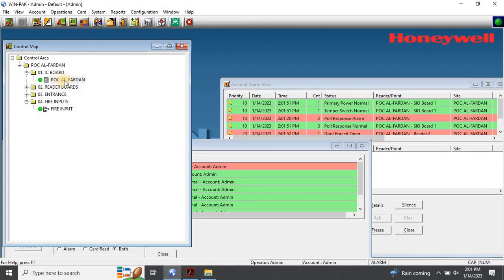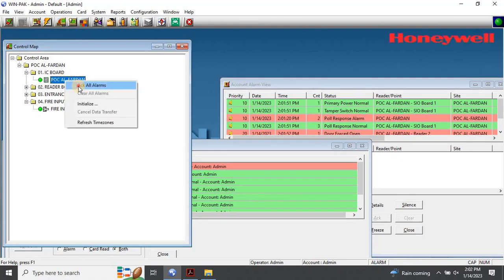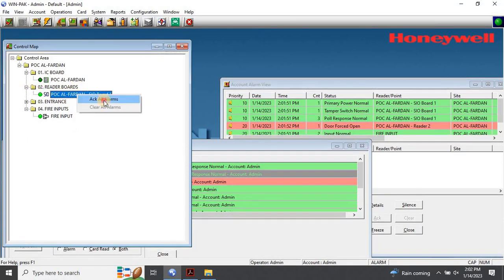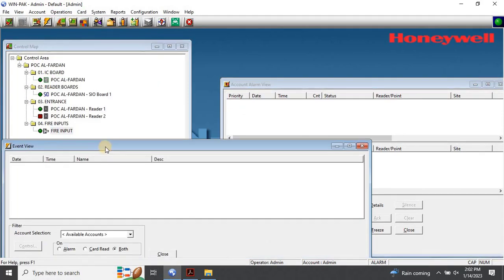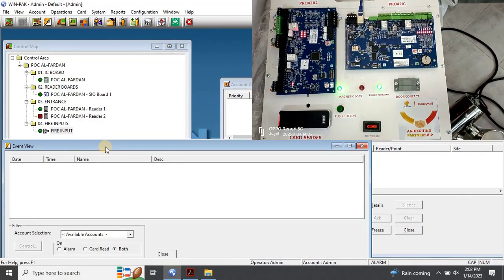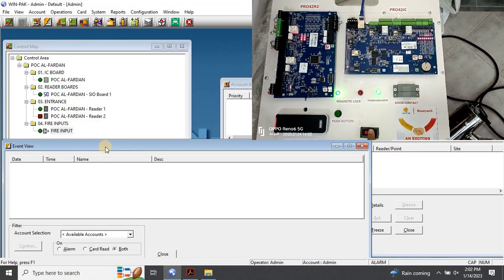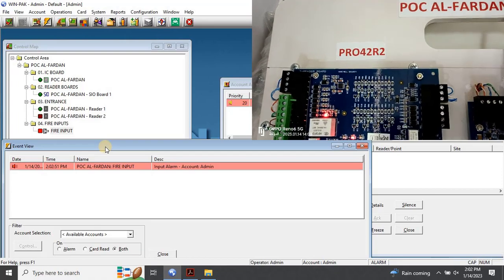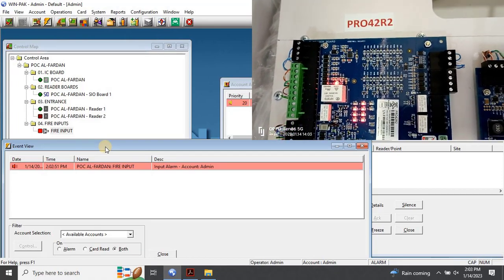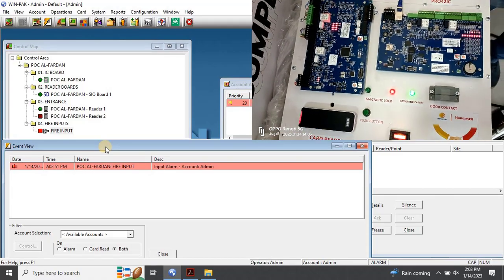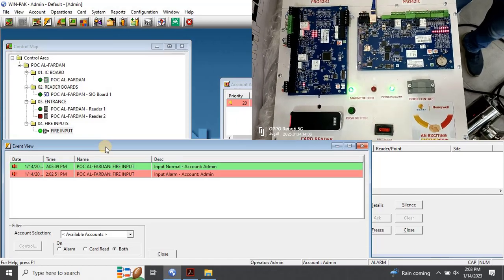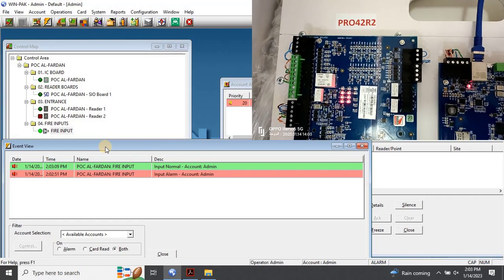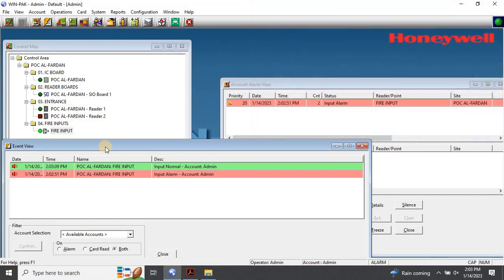Once the initialization is completed, it's time to test the fire alarm interface with the access control system. Before we begin, let's clear all the events for a fresh start. As you can see on the board, once I turn on the fire alarm input switch, the relay is activated and the automatic alarm is generated. The fire input is activated and the fire input indicator changes from green to red on the control map. When I turn off the fire alarm input, it returns to a normal state and the indicator becomes green again.